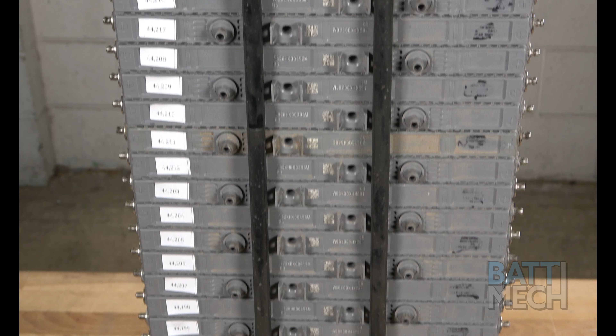This is how the modules should look from the other side of the battery pack, with a positive module mark on the top to the left. The modules should alternate between positive and negative as they descend within the compression block, and should rotate from non-vent to vent. If you have two vents on top of each other, your modules are out of order. The same is true if you have two positives or two negatives on top of each other.